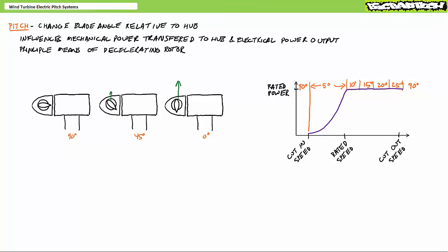Between the cut-in to the rated speed, the turbine sets the pitch angle of the blades such that they intercept the maximum amount of incoming power. Depending upon the aerodynamic profile of the blades employed, you might observe a pitch angle of, let's say, 5 to 6 degrees from the cut-in speed to the rated speed. This being said, there's a practical limit to the capacity and lifespan of the mechanical and electrical components comprising the turbine, and beyond the rated speed, the turbine starts taking active measures to protect itself and ensure its longevity.